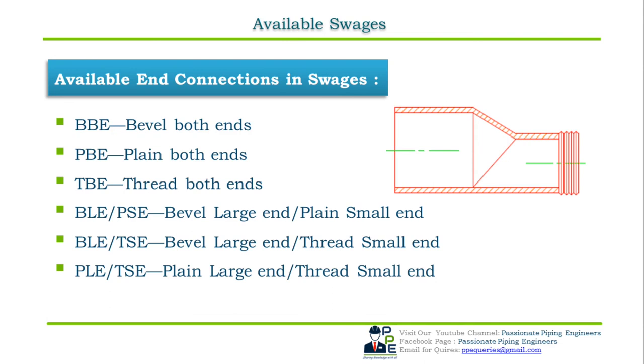Swedges with both ends beveled are for direct connection to butt welded fittings or bevel-ended pipes. Socket welded swedges have plain ends on both sides to be inserted into sockets, or one side plain and one side beveled for butt welded fittings with large bore ends. Threaded swedges have male thread ends on both sides for threaded fittings, or one end threaded and the other beveled for butt welding with large bore pipes.